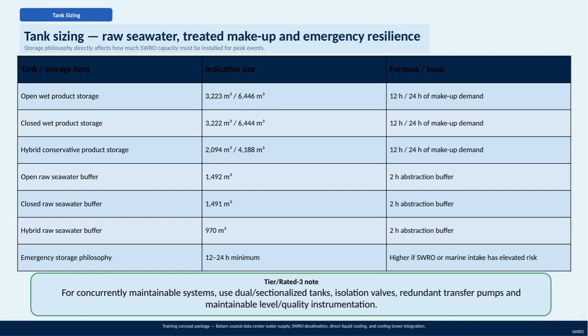When it comes to tank sizing for our Batam Coastal Data Center water supply, we focus on storing raw seawater, treated makeup water, and ensuring emergency resilience. The way we size these tanks has a direct impact on the amount of SWRO capacity required to handle peak demand events. Looking at the different storage options, we have open wet product storage and closed wet product storage, both sized around 3,000 to 6,000 cubic meters, depending on whether we plan for 12 or 24 hours of makeup demand. There's also a hybrid conservative product storage option, which is slightly smaller, designed for the same time frames.